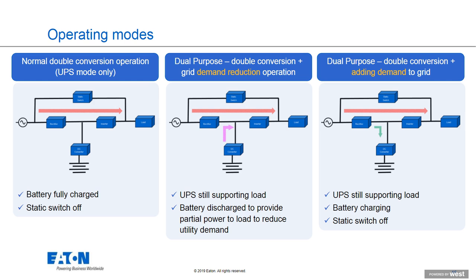Now keep in mind, this is not a heavy, high-intensity discharge like we would do during a power outage. Think of it more as skimming off a little bit of energy or a little bit more energy that's available as excess within that battery. So it's not something that's going to be necessarily over in 5 minutes. I might be able to do it for 20 minutes or 30 minutes or longer. Again, a very shallow battery discharge occurs, and at no point do we go below the minimum amount of battery to support the data center.